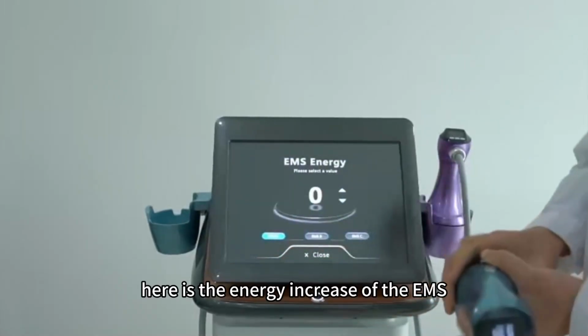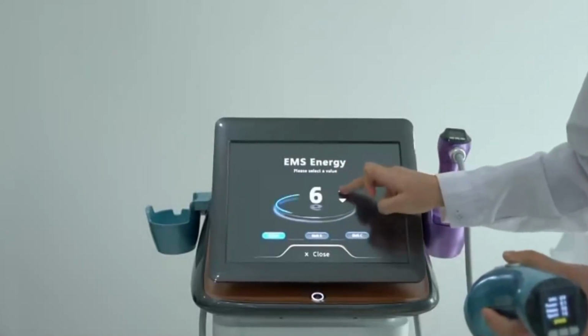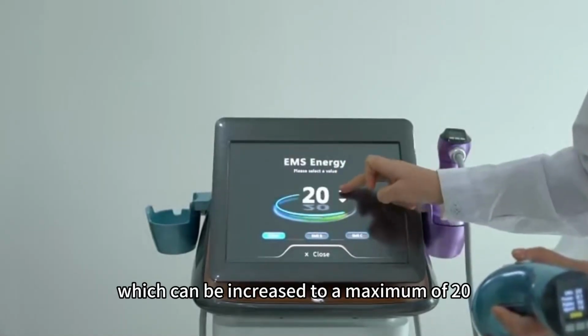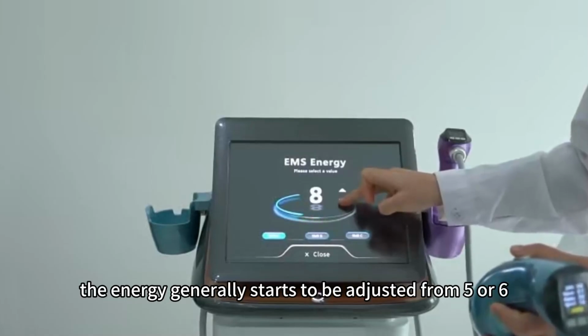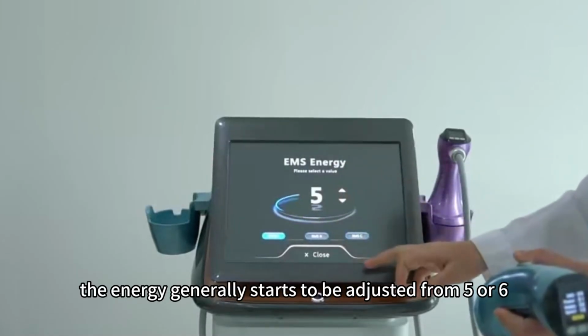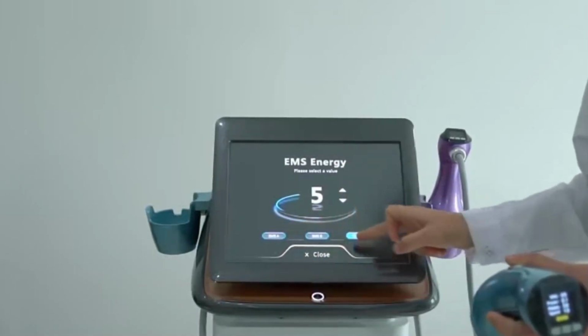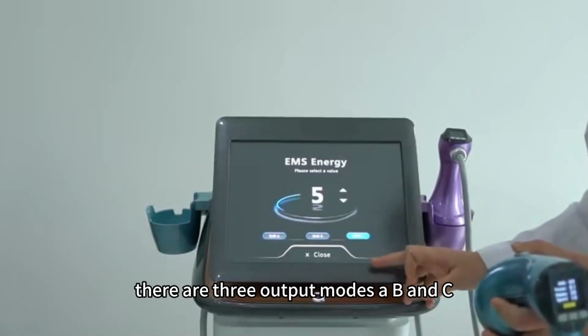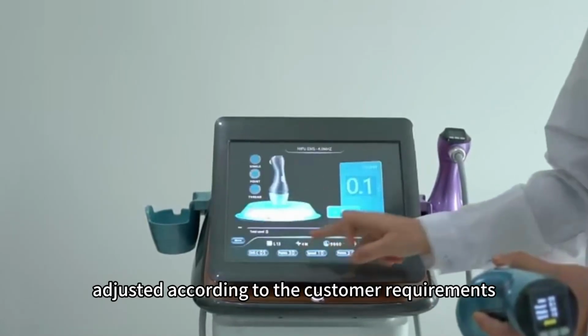Here is the energy increase of the EMS, which can be increased to a maximum of 20. The energy generally starts to be adjusted from 5 or 6. There are 3 output modes, A, B, and C, adjusted according to customer requirements.